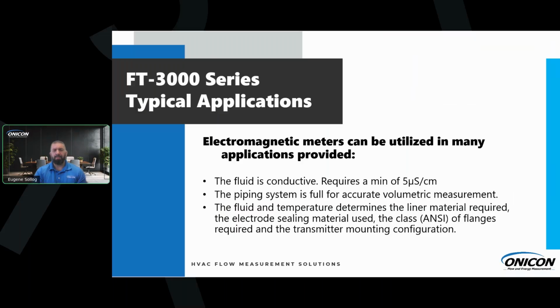So looking at some typical applications, this can be used in so many different applications, providing the below is fulfilled. Again, we're looking at a conductive fluid moving through a magnetic field, so we need conductive water. It cannot be RO water, DI water, or anything below 5 microsiemens. So that's the minimum conductivity for these meters. The piping system also needs to be full, always a full pipe.